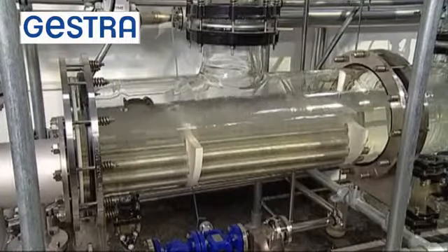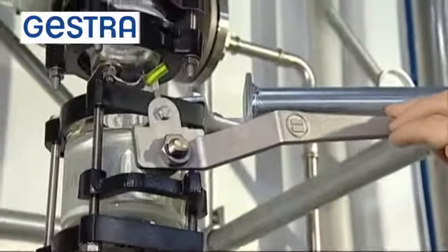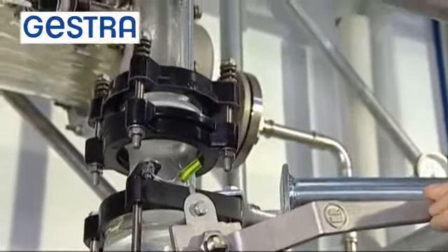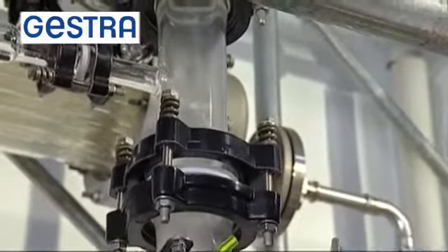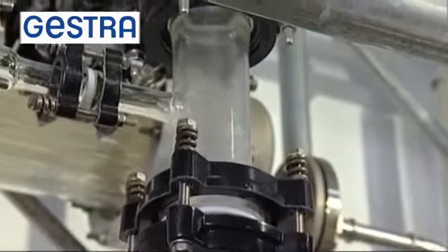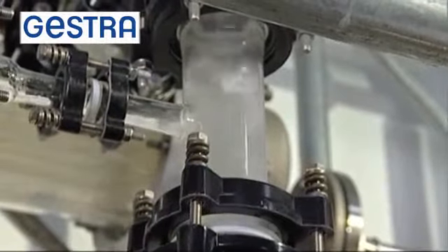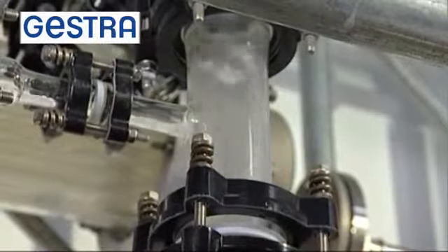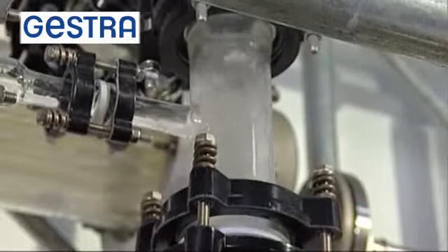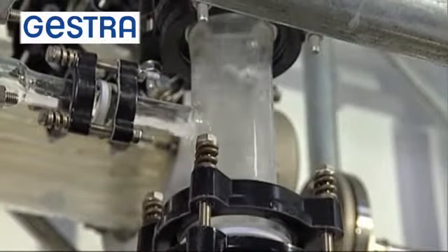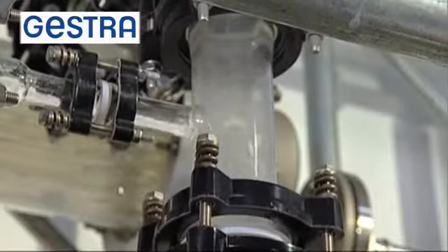Now the steam outlet is opened and steam is introduced into the glass heat exchanger. Initially, the steam condenses quickly and becomes visible, a condition which arises in precisely the same way in every steam line during every startup process. Condensate forms and is carried or entrained with the flow of steam. After a short while, the glass components have been heated up and the steam then flows invisibly upwards.